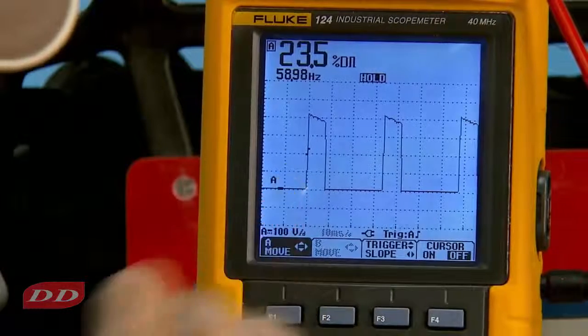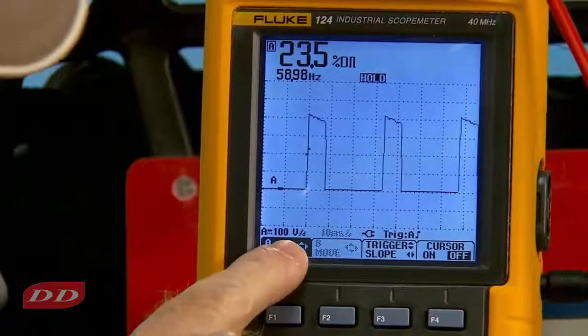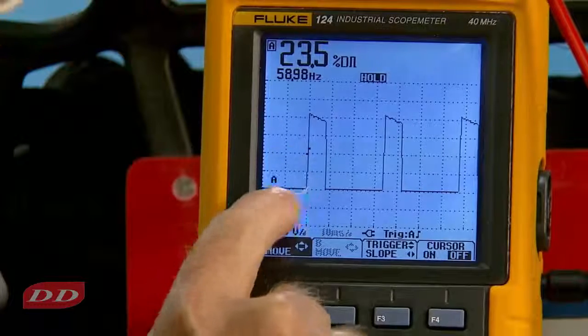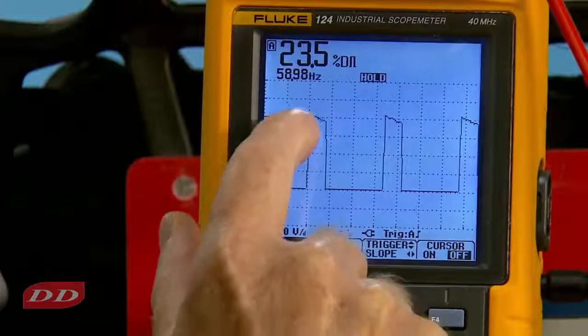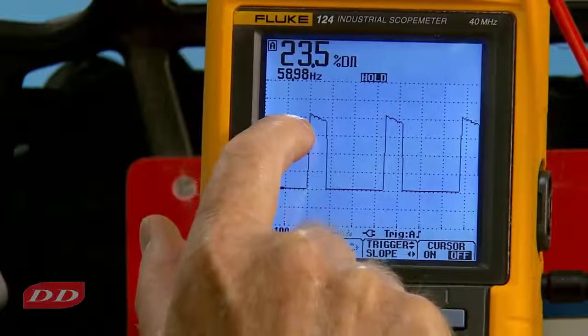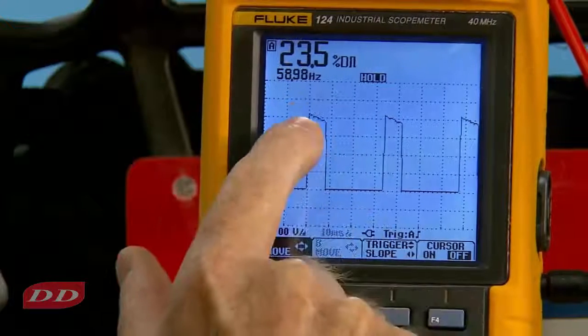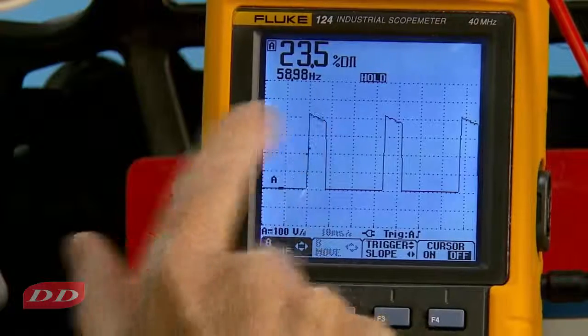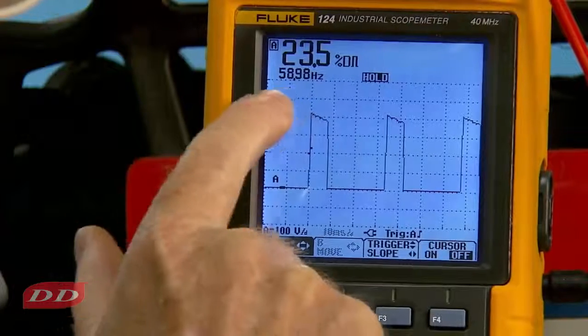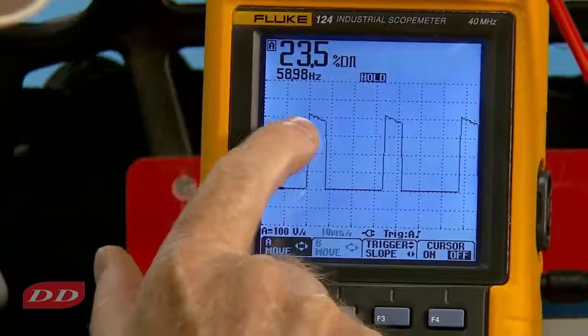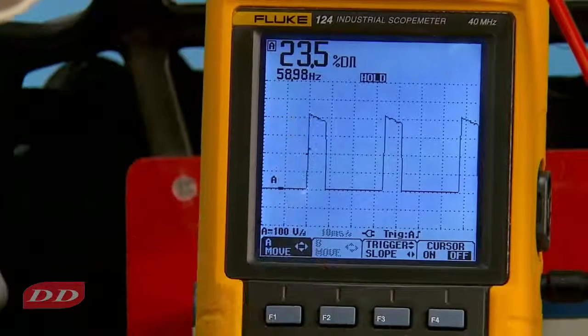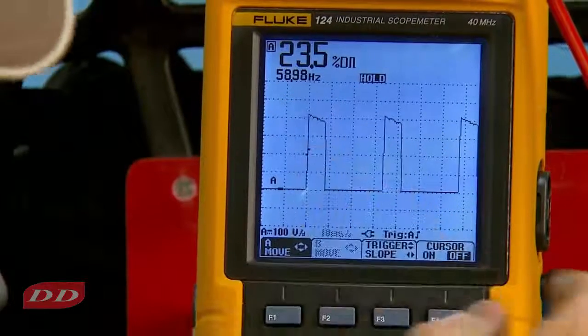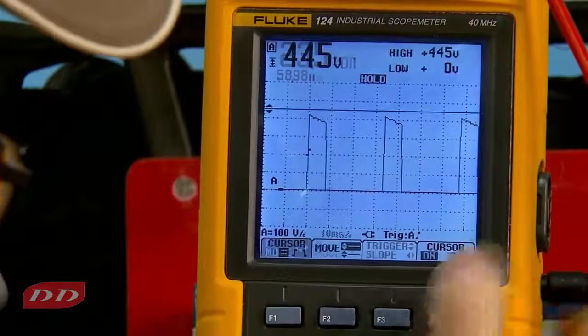The scale is set at 100 volts per division vertically. So this is a zero line, 100, 200, 300, 400. 450 is what we dialed in. As you can see, the top of the waveform did not get to the 450 mark, but at the very tip it just exceeded the 400 mark. So let's take a look at this, and we'll put our cursors back on.